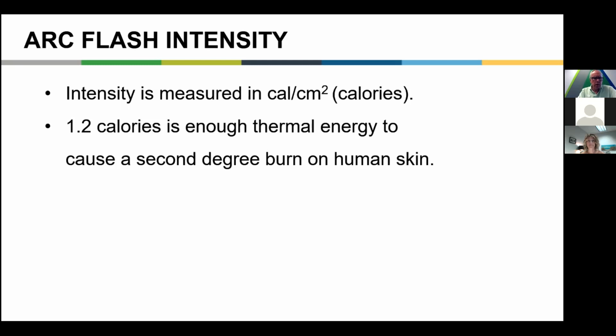The way we look at it in terms of injury is if it's less than 1.2 calories, it's approximating a Band-Aid event, an event where someone might go to the hospital, but they probably won't be admitted. And over 1.2 calories, it quickly becomes dangerous enough that a person would need to be transported to a burn center, a specialized medical facility to treat terrible arc flash burns.